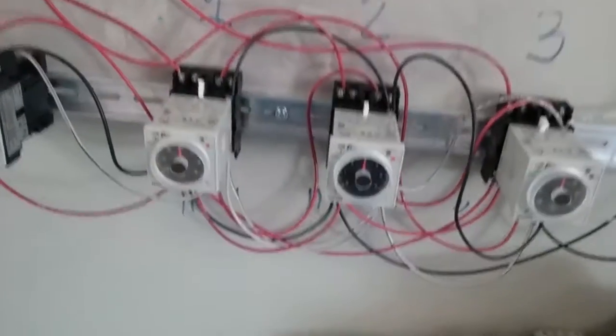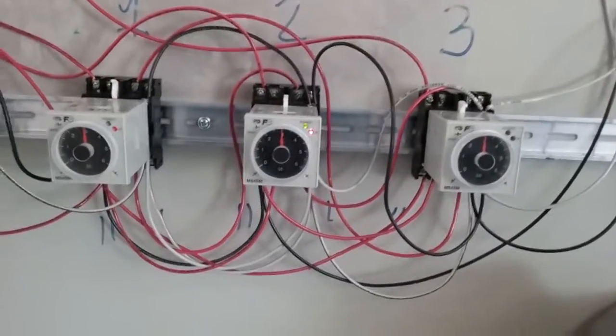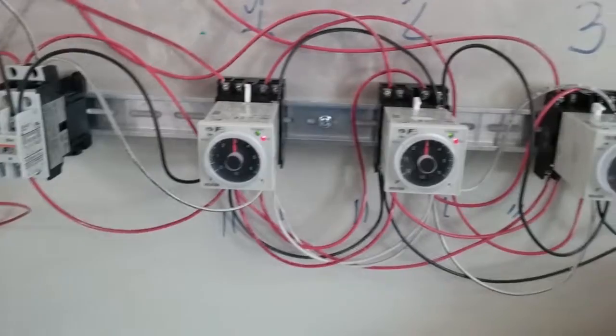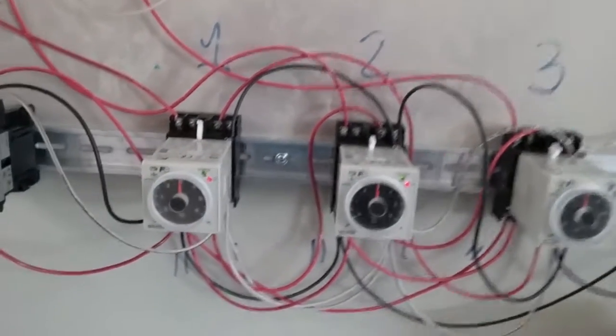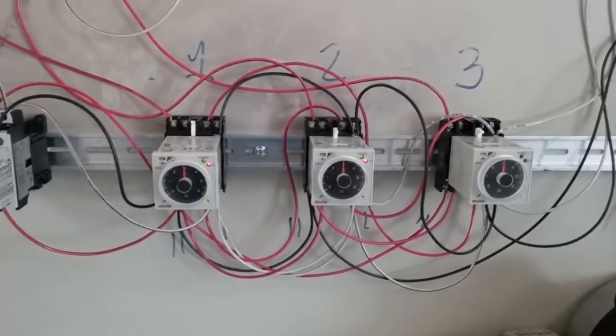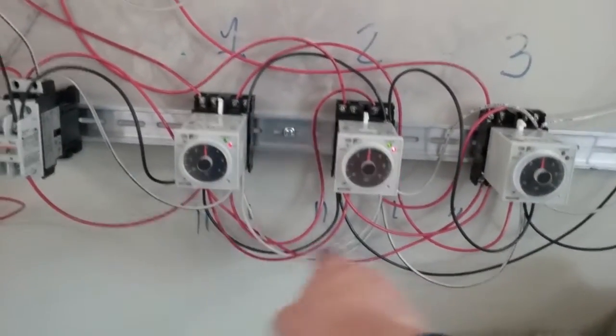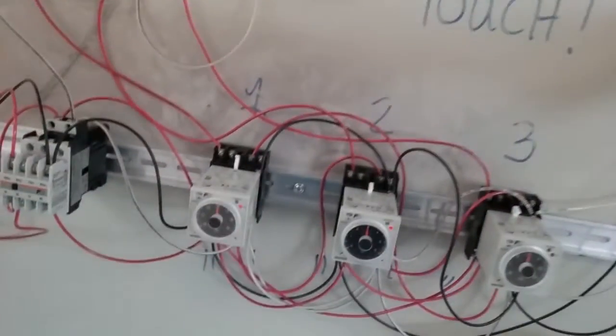So in this particular application, we have the hotline going to all of the timer power inputs, which is pin 10 for you technical people on these timers. Pin 2 then is the neutral, and you can see that all the neutrals are connected together to L2 as well.